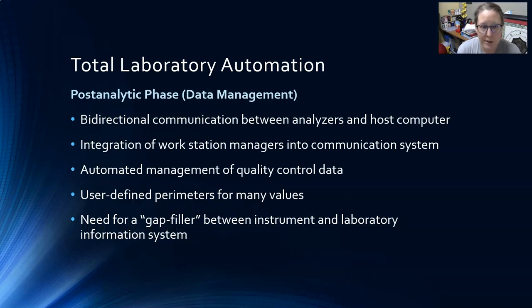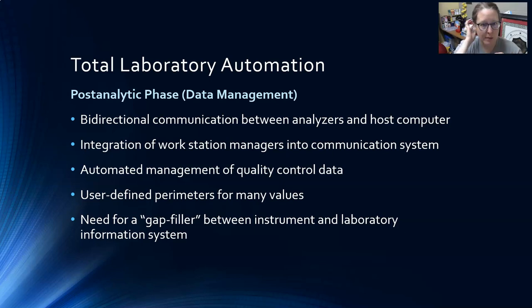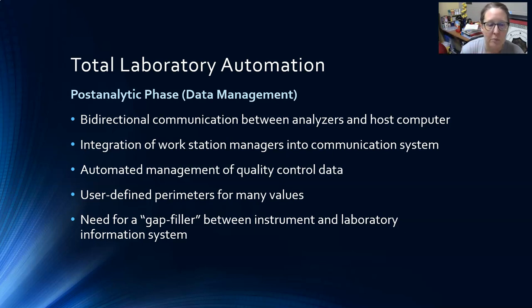The post-analytic phase — or data management phase — of total lab automation includes bi-directional communication between analyzers and the host computer, which may be a middleware or a lab information system. Integration of workstation managers into the communication system allows a computer to manage multiple analyzers and alert a tech to problems at specific instruments. There is automated management of quality control data, which is very useful given the high volume of data generated.